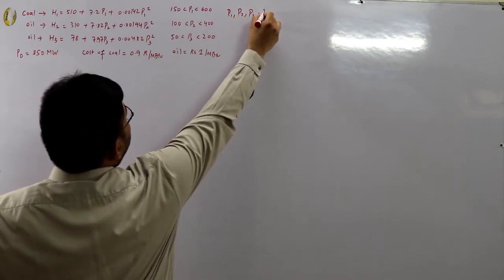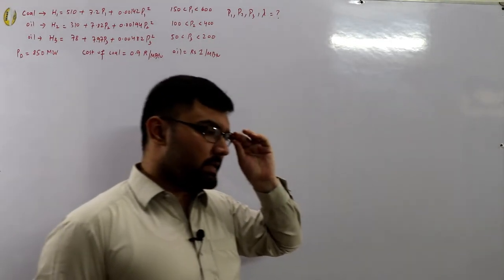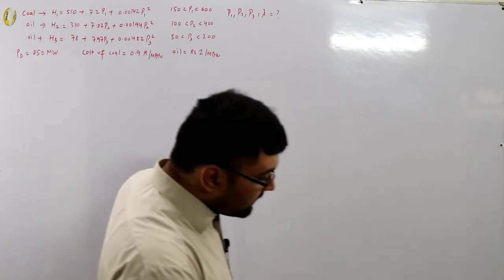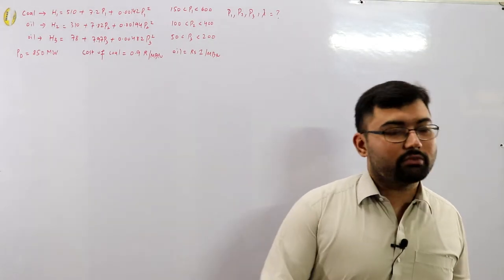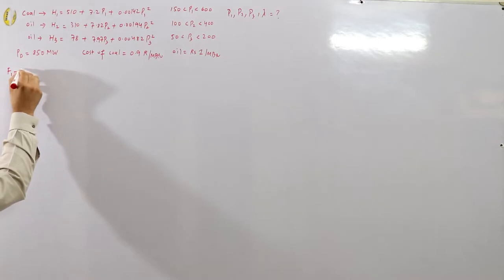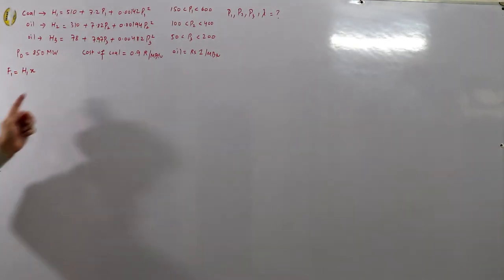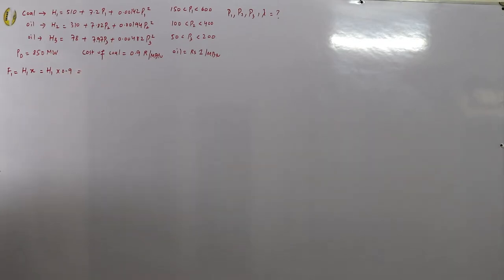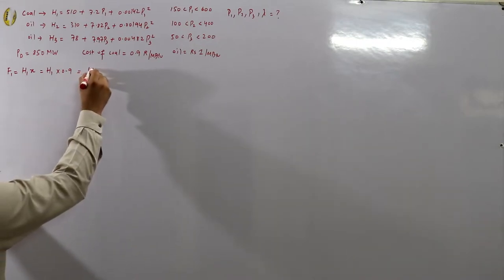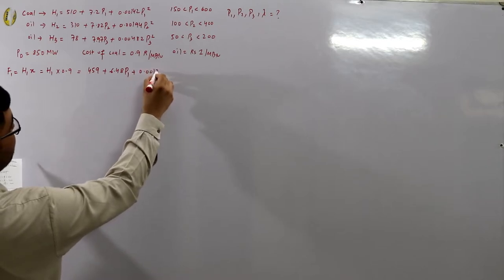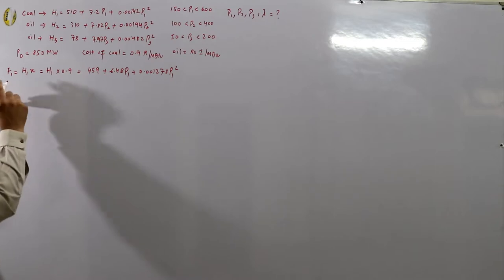Previously we took the cost of coal as 1.1, and in that case p1, p2, p3 lay within the economical range. Today's purpose is to get values outside the economical range. First, find the f functions: f1 = h1 × 0.9 = 459 + 6.48·p1 + 0.001278·p1². Since oil cost is 1, f2 = h2 and f3 = h3.